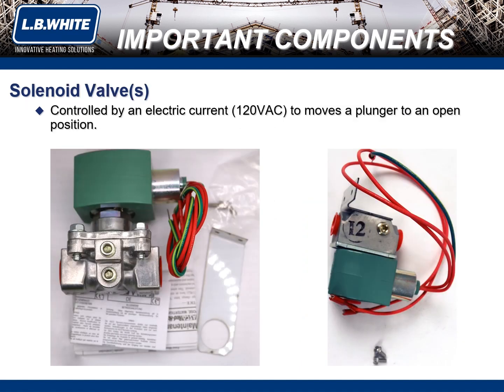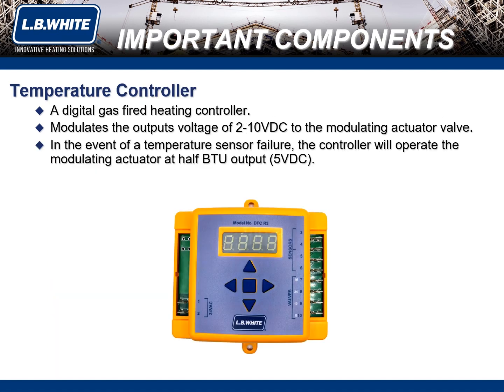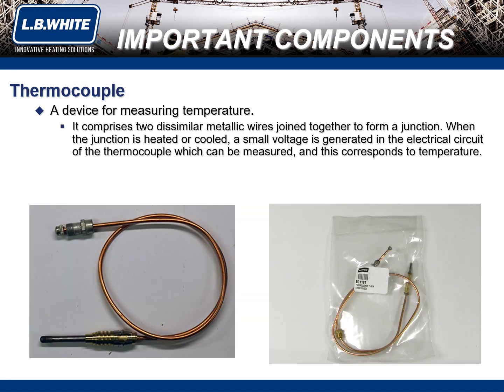Solenoid valves are dual valves controlled by an electric current, 120 VAC, to move a plunger to an open position. A temperature controller is a digital gas-fired heating controller that modulates the output voltage of 2 to 10 VDC to the modulating actuator valve. In the event of a temperature sensor failure, the controller will operate the modulating actuator at half BTU output, 5 VDC.